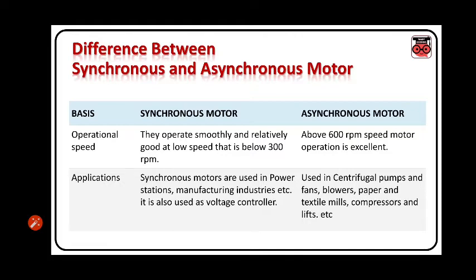Next is operational speed. Synchronous motors operate smoothly and are relatively good at low speed, that is below 300 RPM. Whereas in asynchronous motor, above 600 RPM speed, motor operation is excellent. Applications: synchronous motors are used in power stations, manufacturing industries, etc. Whereas asynchronous motors are used in centrifugal pumps and fans, blowers, paper and textile mills, compressors, and lifts, etc.